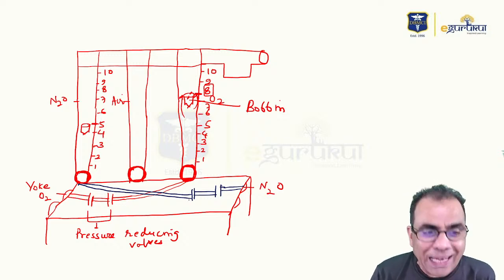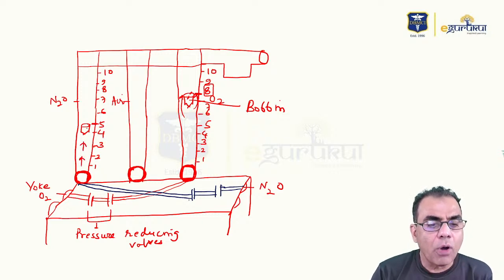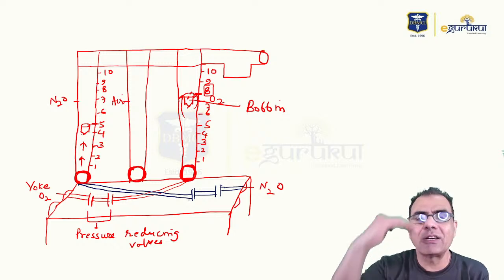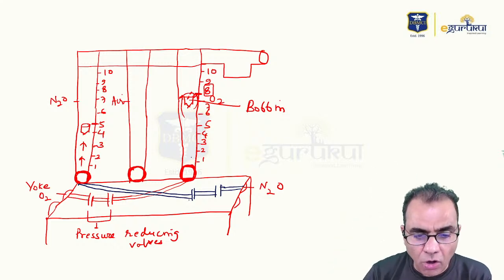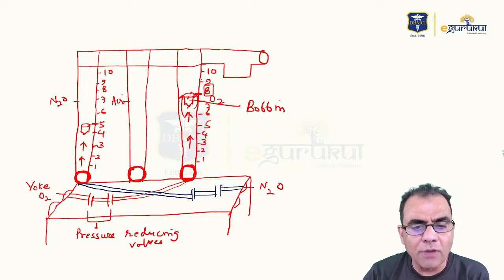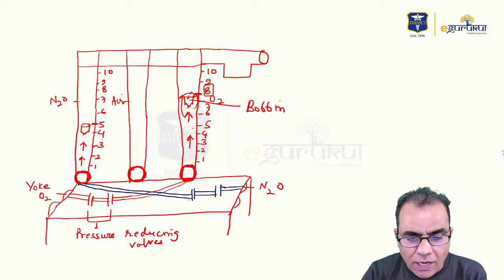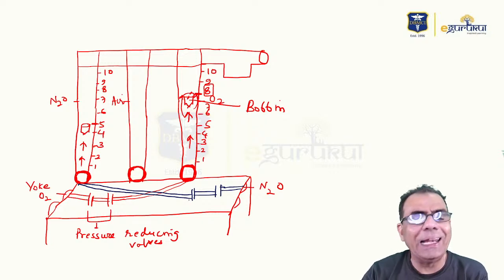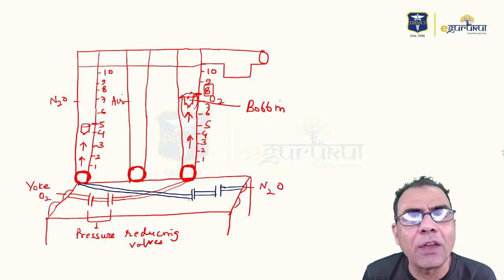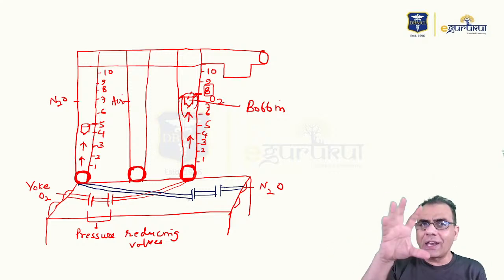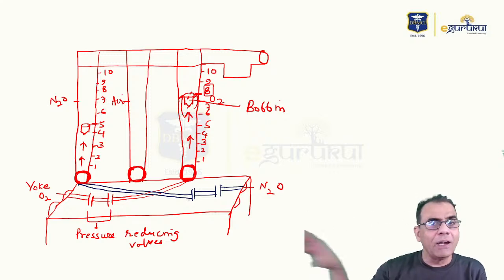If I want to increase nitrous oxide, I will rotate this knob. More gas will come and the bobbin will go up. And that is how we can set the flow rate. Or I want to increase the oxygen, I'll rotate this. I want to give, say, 9 liters. So I will rotate it, the bobbin will go up, and at the point when the bobbin reaches 9 liters, I will stop. That is how I am setting my flow. Now, how much flow we keep in the anesthesia machine, that we'll discuss later.